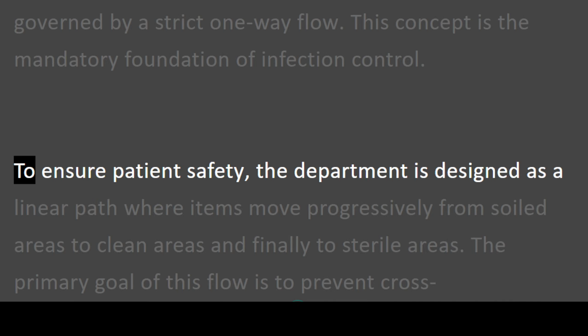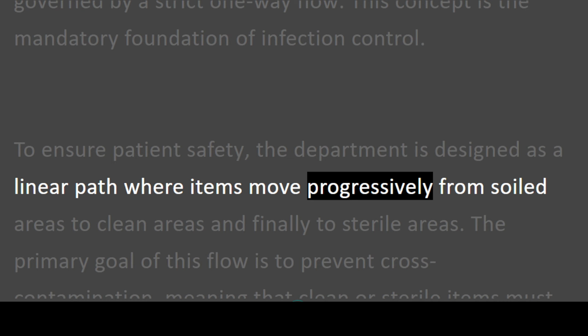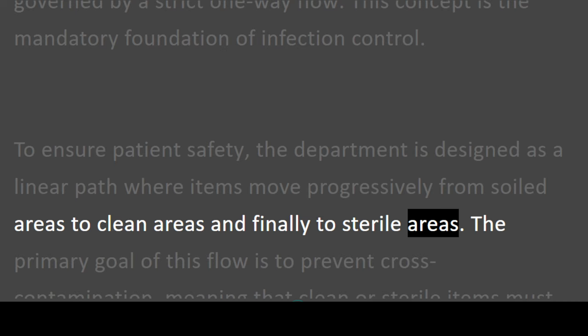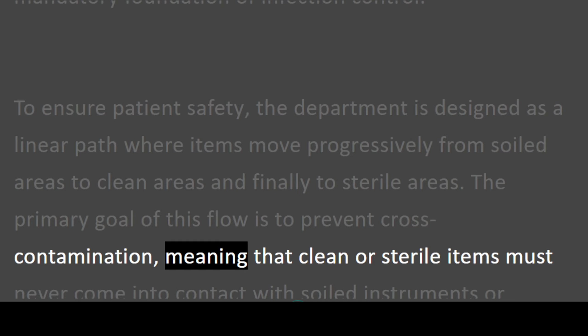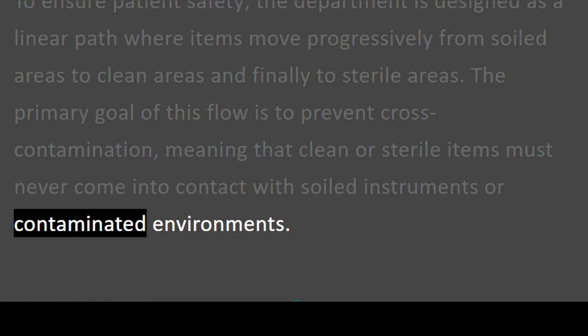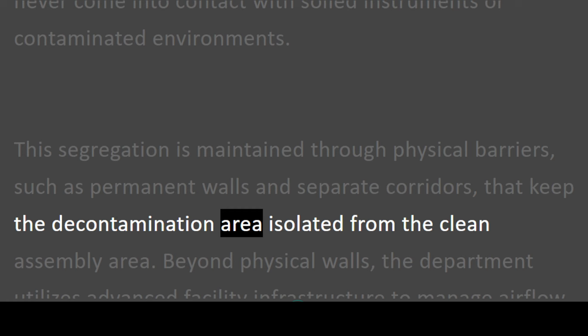To ensure patient safety, the department is designed as a linear path where items move progressively from soiled areas to clean areas and finally to sterile areas. The primary goal of this flow is to prevent cross-contamination, meaning that clean or sterile items must never come into contact with soiled instruments or contaminated environments. This segregation is maintained through physical barriers, such as permanent walls and separate corridors, that keep the decontamination area isolated from the clean assembly area.